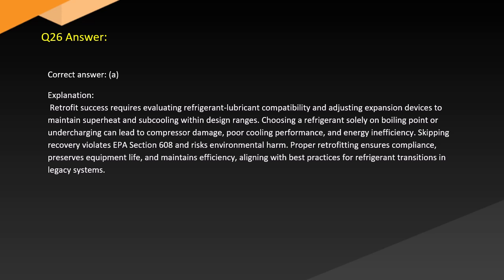Answer. Correct answer. A. Explanation. Retrofit success requires evaluating refrigerant lubricant compatibility and adjusting expansion devices to maintain superheat and subcooling within design ranges. Choosing a refrigerant solely on boiling point or undercharging can lead to compressor damage, poor cooling performance, and energy inefficiency. Skipping recovery violates EPA Section 608 and risks environmental harm. Proper retrofit ensures compliance, preserves equipment life, and maintains efficiency, aligning with best practices for refrigerant transitions in legacy systems.